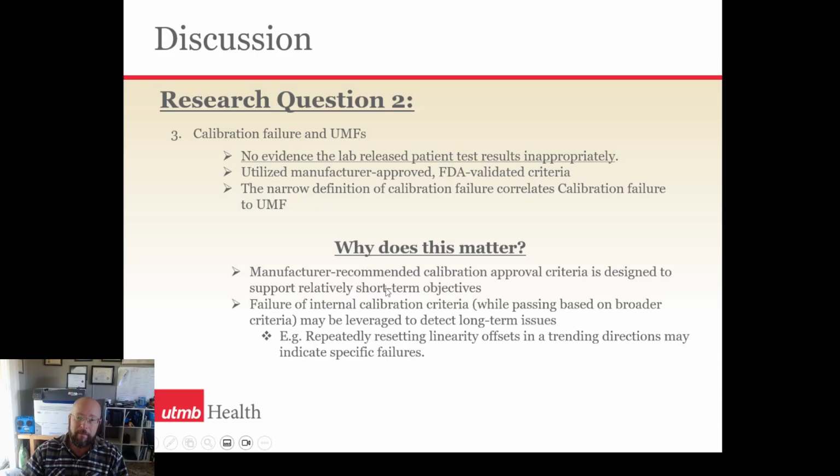And why does this matter? Of course, the manufacturer-recommended calibration criteria is designed to support short-term objectives. In other words, does your calibration provide clinically relevant data within the next, say, 45 days? That's what they're interested in. I'm interested in, does it provide relevant data that ties back to mechanical failure? Two different objectives here. Failure of internal calibration criteria may be leveraged to detect long-term issues.